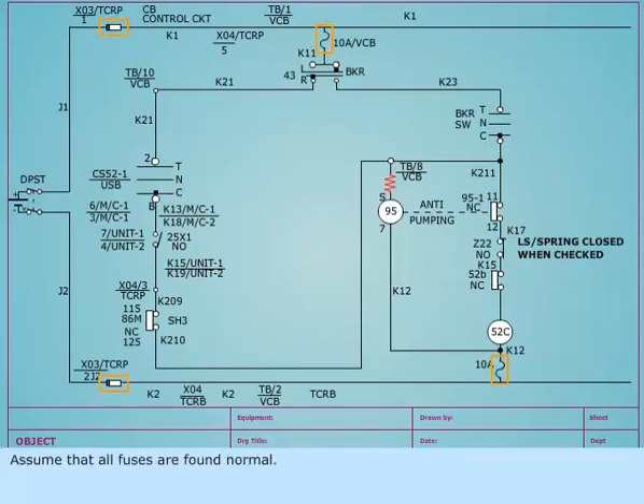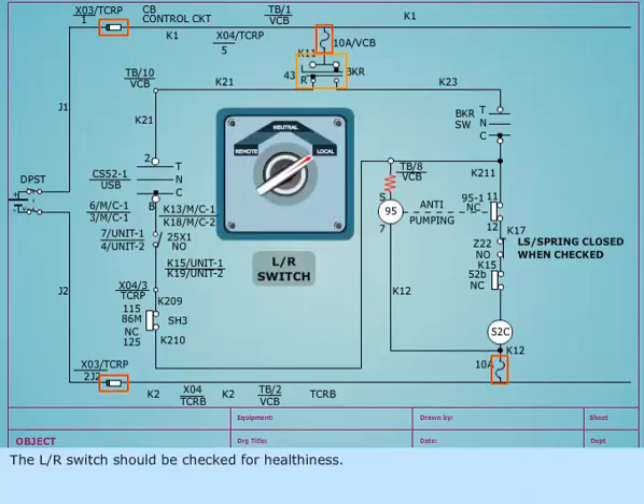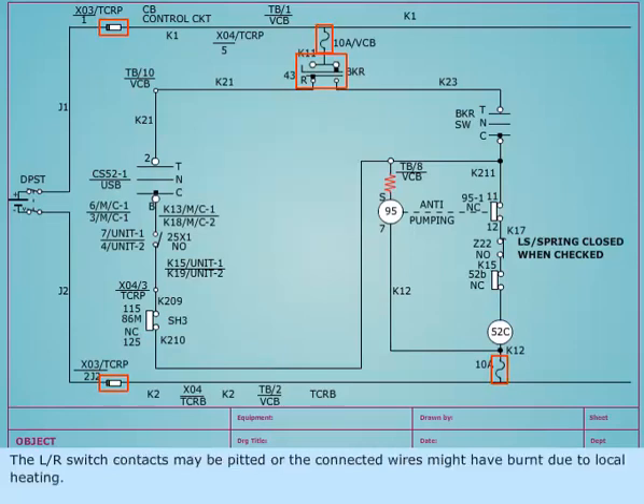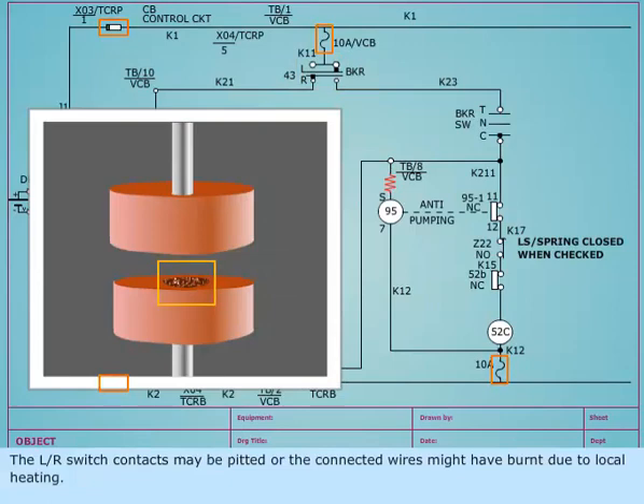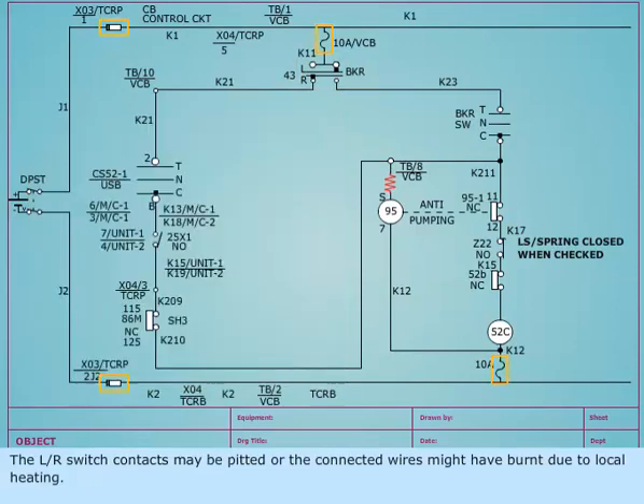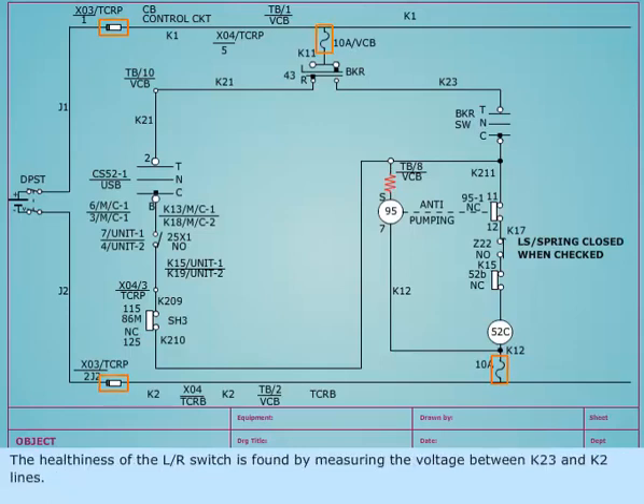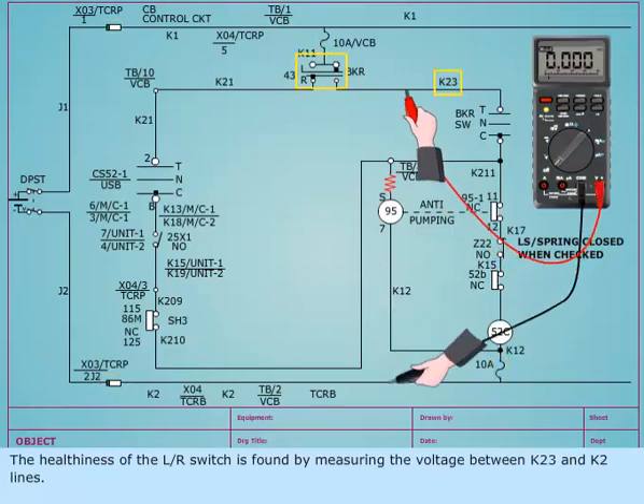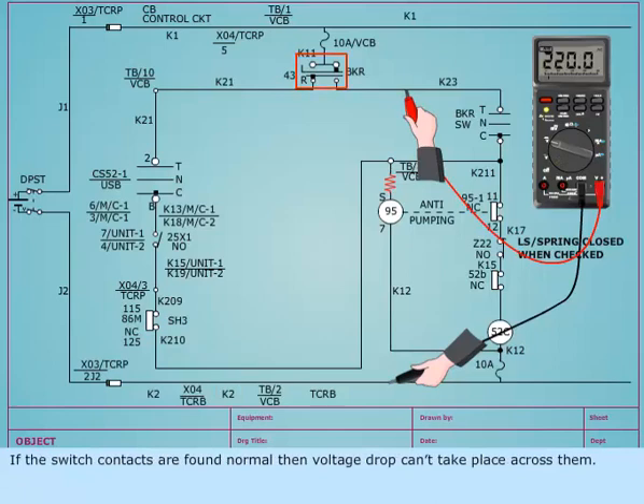Assume that all fuses are found normal. The L/R switch should be checked for healthiness. The L/R switch contacts may be pitted or the connected wires may have burnt due to local heating. The healthiness of the L/R switch is found by measuring the voltage between K23 and K2 lines. If the switch contacts are found normal, then voltage drop can't take place across them. Hence, the multimeter shows full supply value.